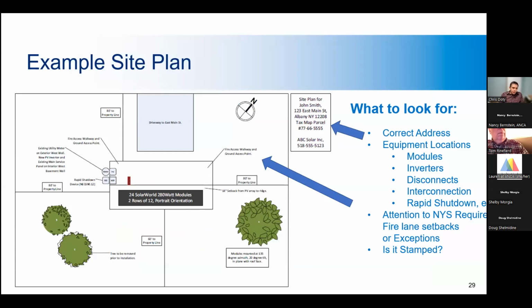All right, so here is an example of a site plan. It's not a perfect site plan, but it's a site plan. And what you want to do is take a closer look at key items. In this one, it's on a rooftop, so you want to make sure that there's rooftop access. You want to verify the location of the meter, the inverter, all of the different components in the solar design. You want to make sure it has the correct address and tax information. And you also want to make sure that the professional engineer or the registered architect has stamped and signed the drawing. And I think that's about it for that one.